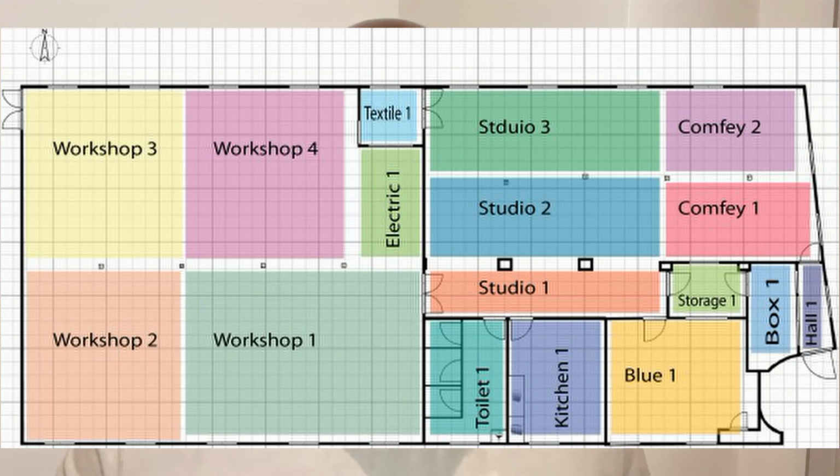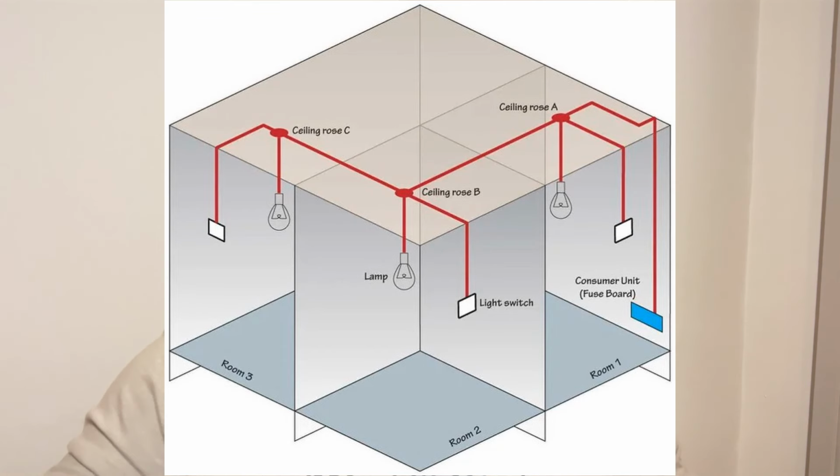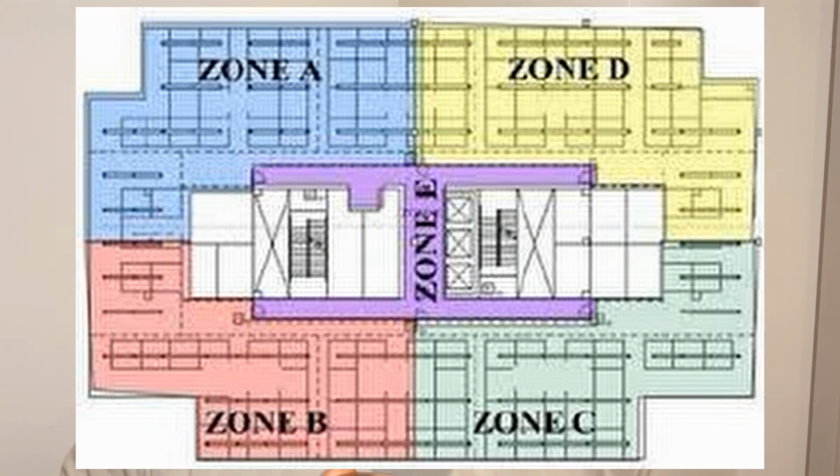Costly mistake number 4: no zoning or future proofing. We went to inspect a house in Mampong just about 2 weeks ago, in the middle of nowhere, in the middle of the forest, really. Lovely house, but for example, the ground floor was all on one lighting circuit. That is poor design. You can't have a whole level all on one lighting circuit.